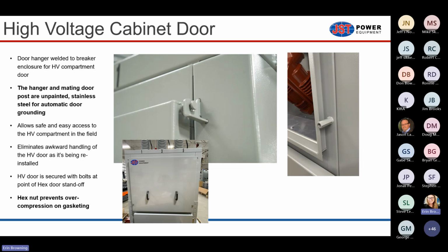It's very light. So it hangs right into the hanger, and then on the bottom of the door we have these standoff hex bolts, and that's how you fasten the high voltage door to the breaker. That hex bolt prevents you from over-tightening when you're bolting in the cabinet door. It prevents you from over-compressing the gasket. So again, that's another design consideration for making sure the gasket is going to do its job over the life of the breaker.